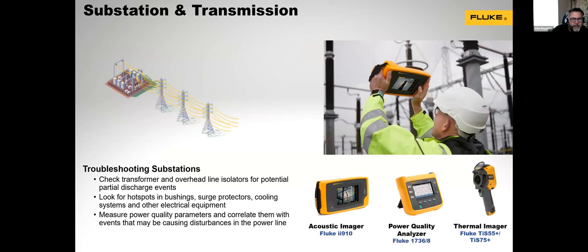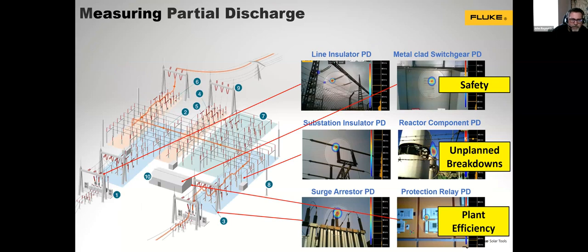If we're looking at substation and transmission, we've also got things like, again, power quality and thermal imaging, but we also now bring in acoustic imaging, specifically the II910, which can look at overhead line isolators for potential discharge. With thermal, you can look for hotspots in bushing, surge protectors, and cooling systems. And again, you can measure power quality parameters and correlate them with events that may be causing disturbances in the power line. Just some of the examples on partial discharge. You can see here we've got substation insulator partial discharge, line insulator discharge, surge arrestor, and also in the panels themselves, you can check these metal clad switchgear, etc., without having to touch the panel itself.